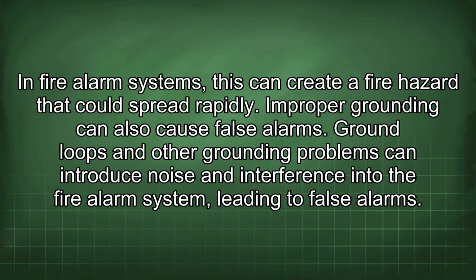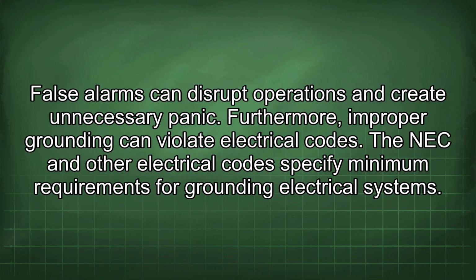Improper grounding can also cause false alarms. Ground loops and other grounding problems can introduce noise and interference into the fire alarm system, leading to false alarms. False alarms can disrupt operations and create unnecessary panic.